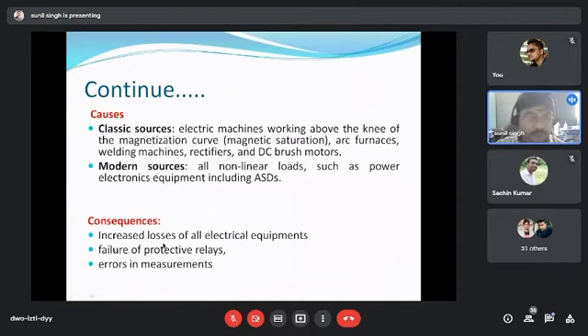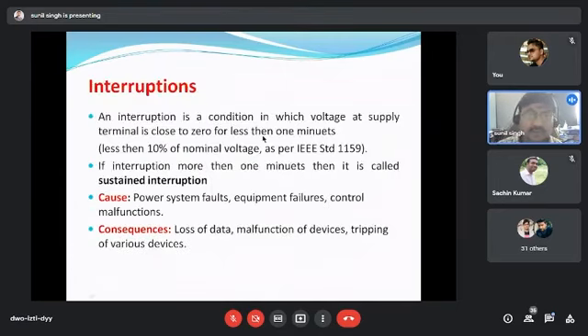What are the consequences of these harmonics? Harmonics may lead to losses in all electrical equipment, failure of protective relays, and errors in measurement. Error in measurement means, for example, when we measure the power factor, we may get a false power factor. Now we have smart meters available that give true RMS readings. What is meant by the true power factor? One is the true power factor, and one is the displacement power factor. The true power factor means the actual power factor, calculated considering the harmonics. It is kilowatt divided by kVA, with kilowatt and kVA both measured when harmonics are present. It is measured by a true power factor meter, with true voltage and current. So incorrect measurement is also there.